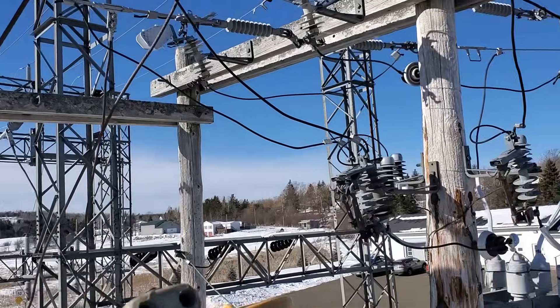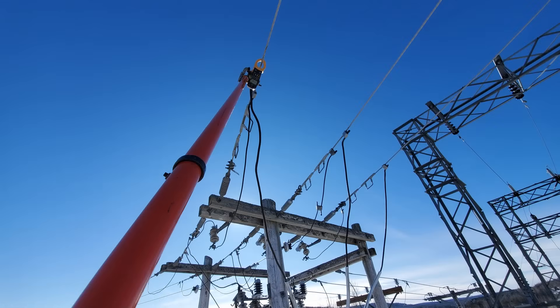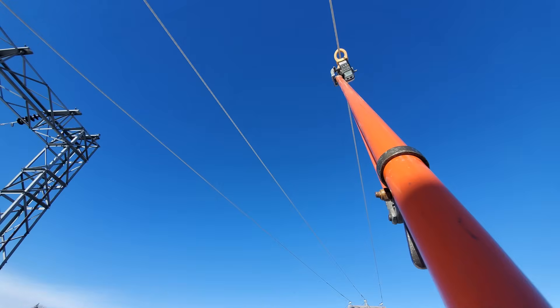That's pretty much it — pretty straightforward stuff. It's good to do when there's more load. It's minus 21 with the windchill. A lot of people out this way use wood heat, so that's not a lot of electrical load for the amount of customers on this part of the line. One thing I forgot to mention: when I said you can use that ammeter on high voltage without the leads, it's safe — but don't ever use it for checking voltage with those leads. That'll blow up in your hands. To check voltage between a phase and the neutral, we have phasing sticks — both analog and digital — that are properly rated for that. Until next time, drop me a fist bump, thanks for watching, and we'll see you next time.